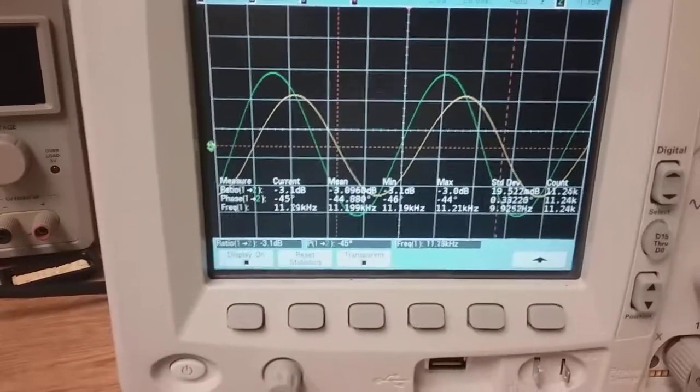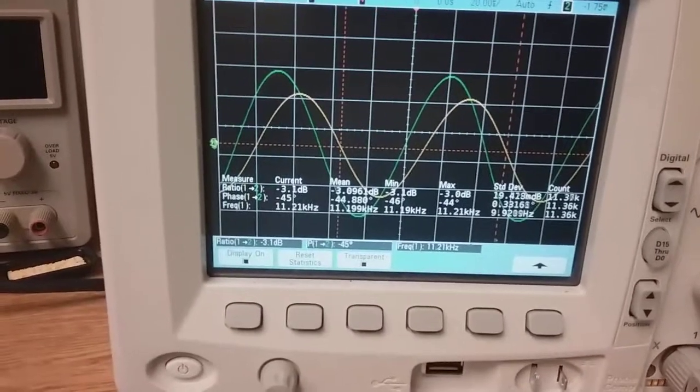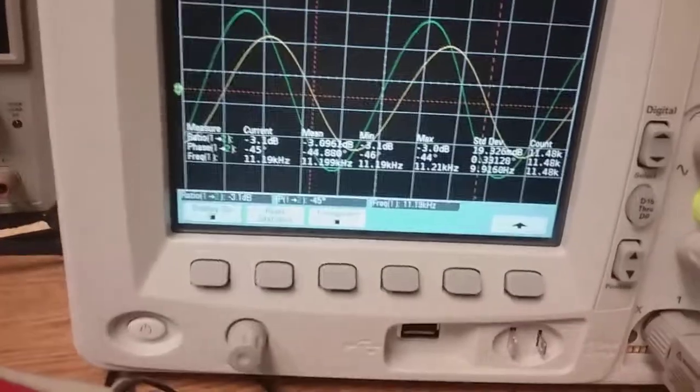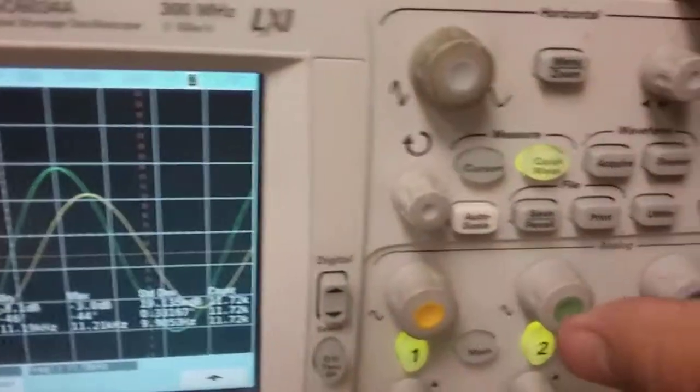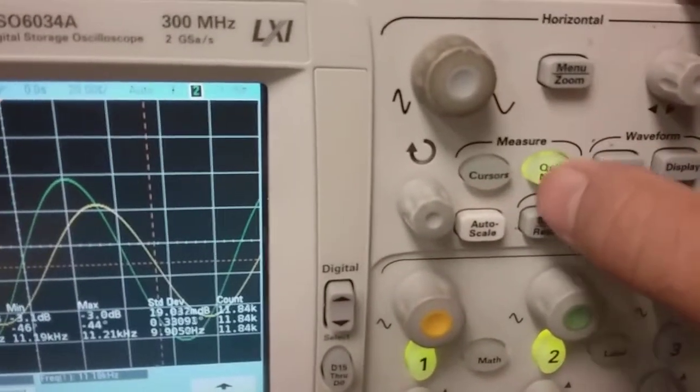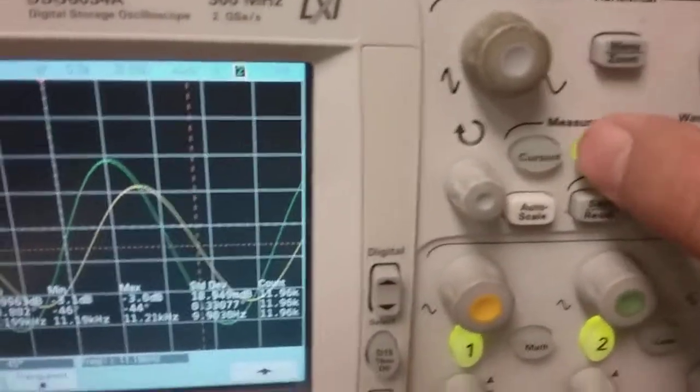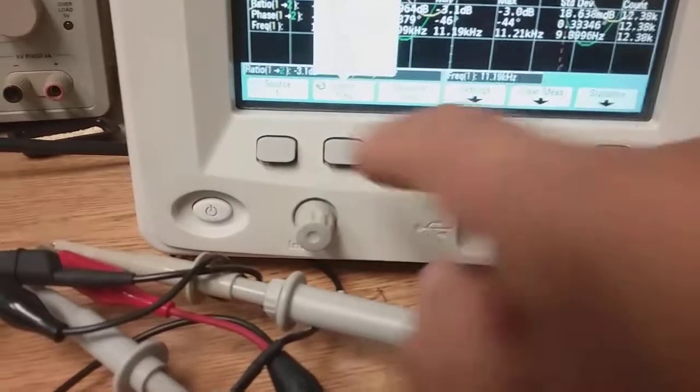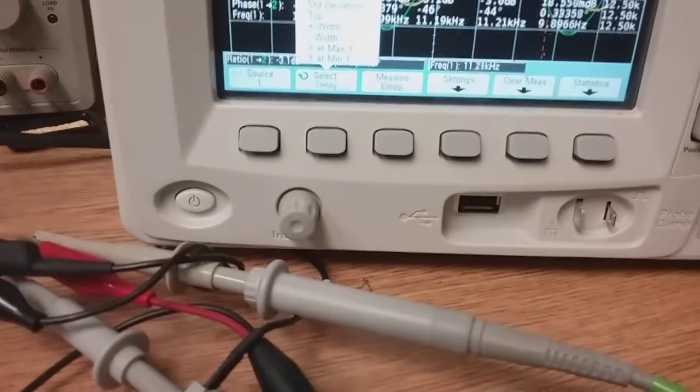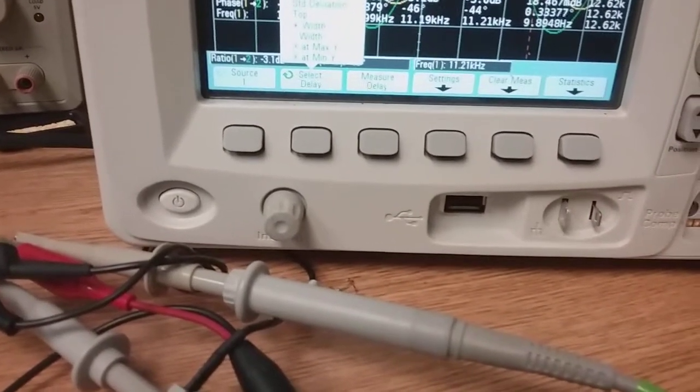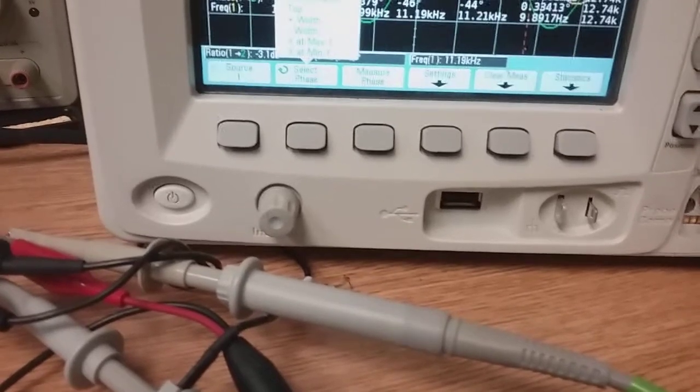Now to take these measurements, really each scope's a little bit different, but there should be a measurement, something like quick measure, and then these things will come up. Which source do you want, and then which function? There's amplitude peak to peak.